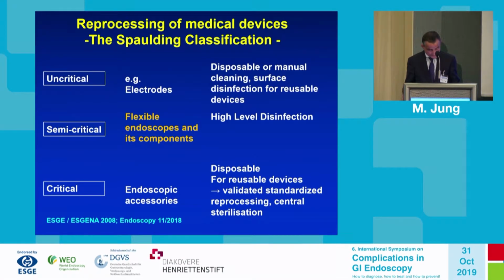So coming back to the basics, flexible endoscopes and their components are regarded as semi-critical devices. Semi-critical tools require only high-level disinfection as a reprocessing process. They must not be sterilized, because in tubular organs, normal flexible endoscopes do not open vessels or lead to mucosal breaks. In contrast, every endoscopic accessory, like polypectomy snares and biopsy forceps, which open up vessels, is regarded as critical. So they have to undergo a validated, standardized sterilization process, or they have to be used as disposables.